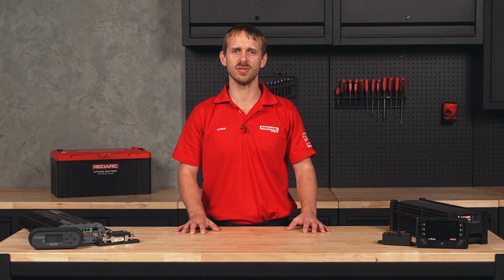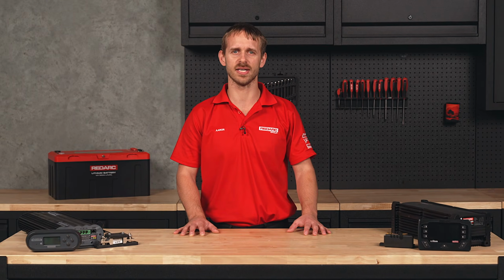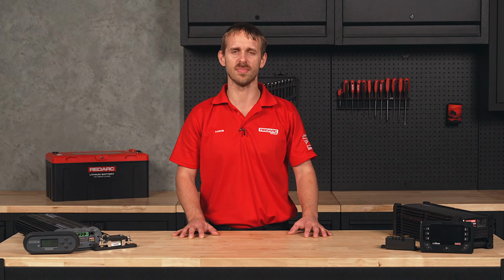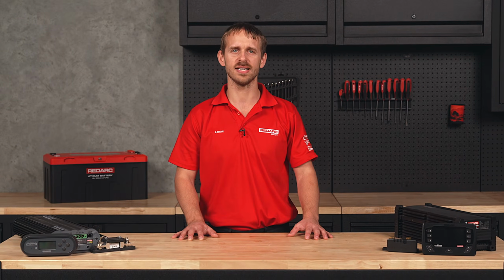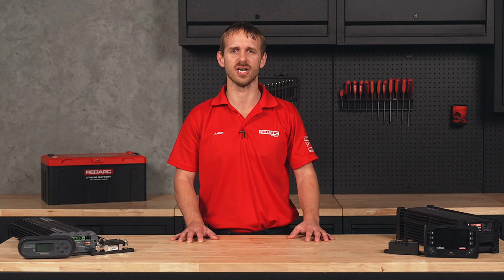If the system is continuing to display calibrating even after the float stage is reached, and less than 0.1 of an amp is flowing to the battery, you will need to undertake a soft reset to restart the charging cycle.